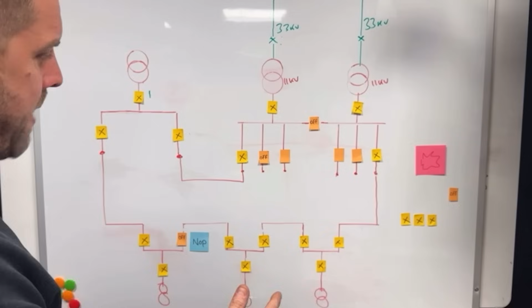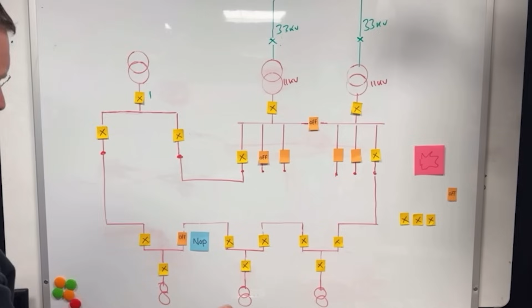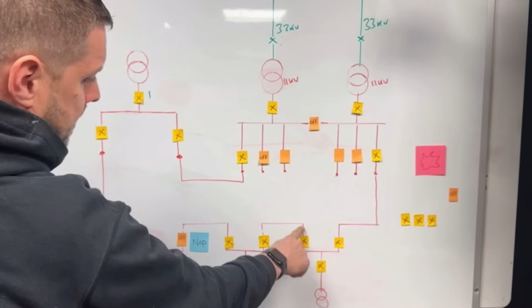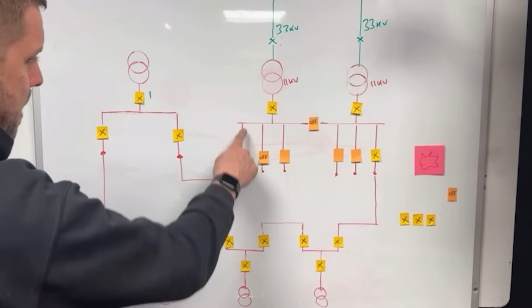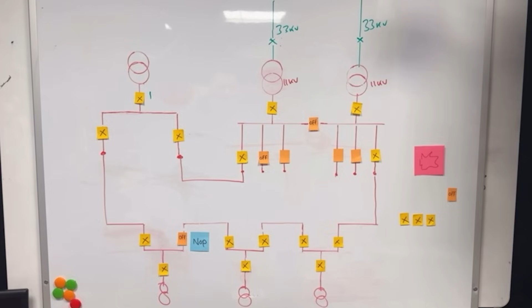So here we've got a typical ring main: 1, 2, 3, 4 transformers, fed from 2 different sides of the board, with a normally open point here. So effectively, as a normal electrician, you'd understand it like this: that comes down there, look, down there, and ends here - that's a radial. And then we've got another radial here, which comes down there and down there. So now we've gone from having a ring main, although it is wired as one, to having 2 radial circuits. But that's not the point, it's not meant to be a ring main.